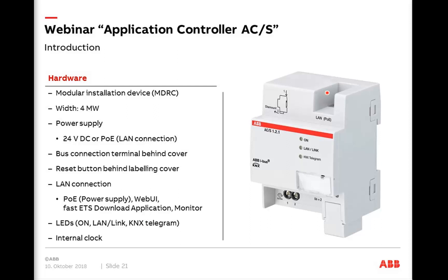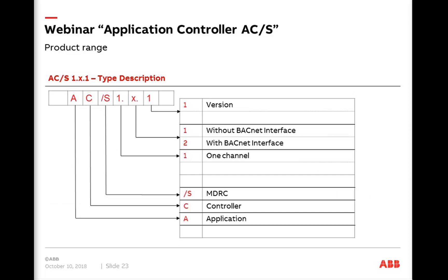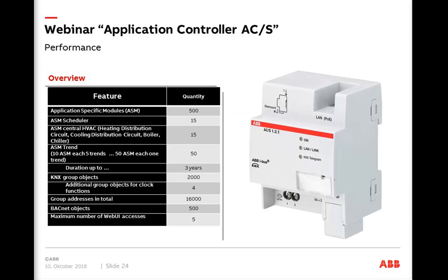LEDs indicate LAN and KNX communication. The ON-LED is normally constantly green. After download or startup, it blinks for about one minute during which there is no web UI access or function — after that it should be constantly green. Time functions require an internal clock, which can be synchronized in three ways: via BACnet, via KNX, or via NTP (Network Time Protocol) from any time server on the internet or local network. Two hardware versions are available: ACS111 without BACnet interface, and ACS121 with BACnet interface.